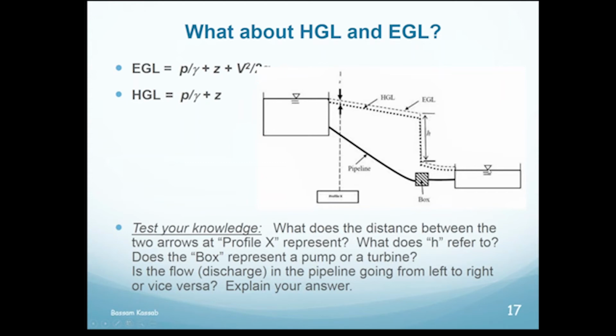However, those who said turbine are correct, but not totally, because this could also have been a valve—if it's closed, open only by 3, 10, or 20 degrees, you could get a huge drop in head. So that's also a possibility here. The answer could be either a turbine or a valve.